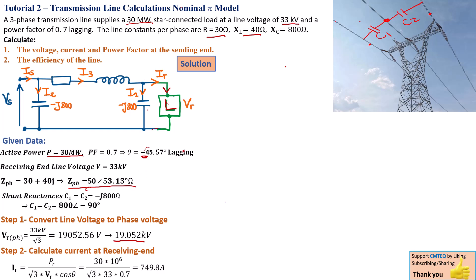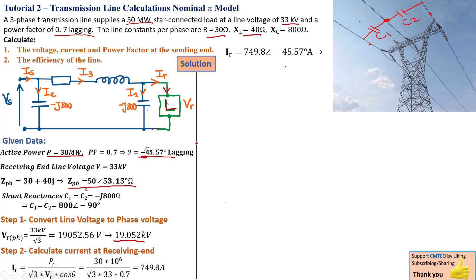Using the power formula, IR equals PR divided by the square root of 3 times VR times cos theta. With PR equal to 30 megawatt, the magnitude of the current at the receiving end is 749.8 amperes. Since the load has a power factor of 0.7 lagging, the angle between voltage and current is negative 45.57 degrees, so our current is 749.8 at an angle of negative 45.57 degrees.